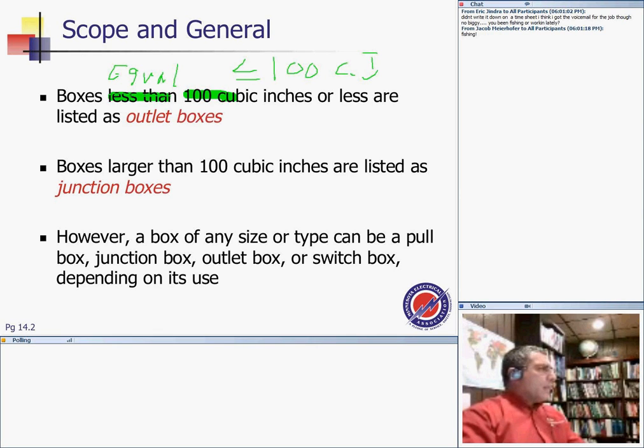So the base is 100 cubic inches, and a box that's equal to or less than that is, for the most part, an outlet box. Now, can I use an outlet box as a J box? Yes, absolutely. Not to use, but you can use it. A junction box, anything larger than 100 cubic inches, my friends, is a J box.